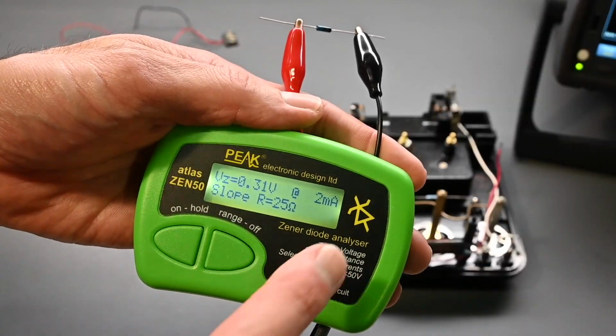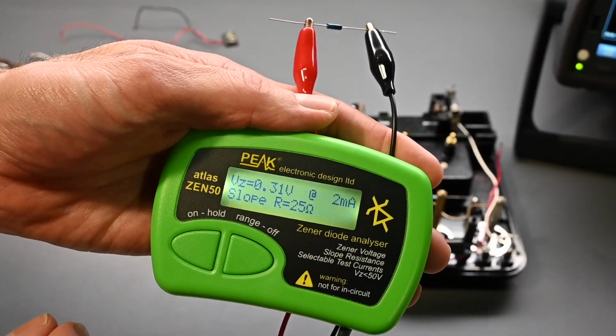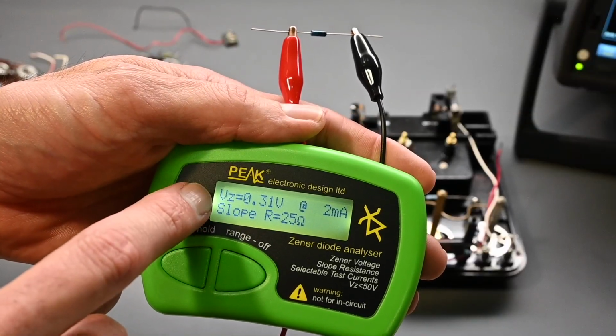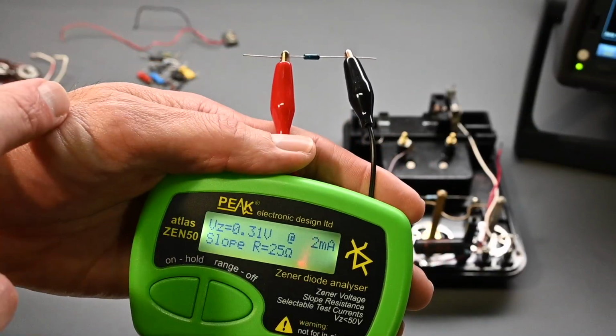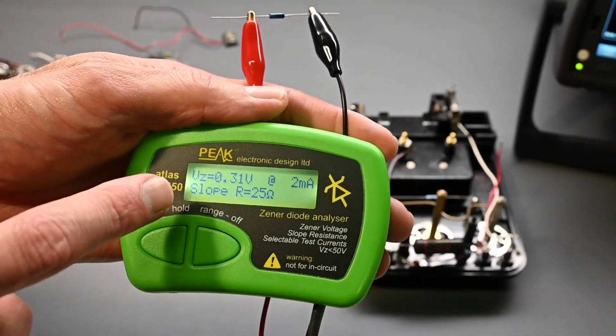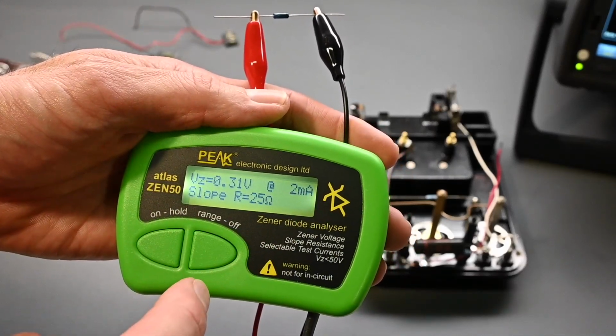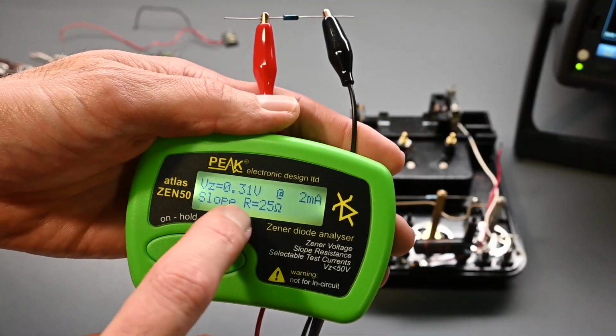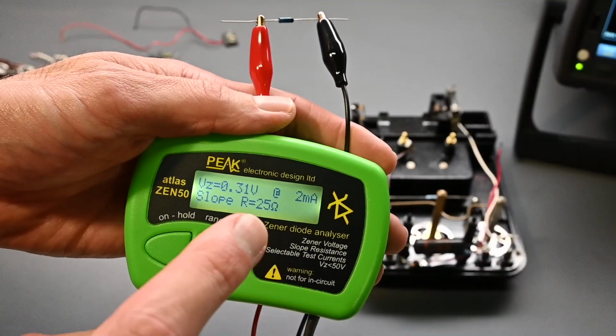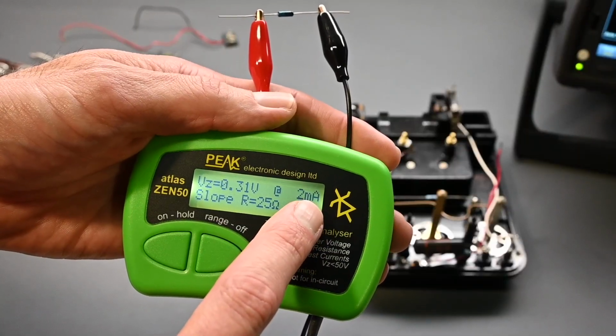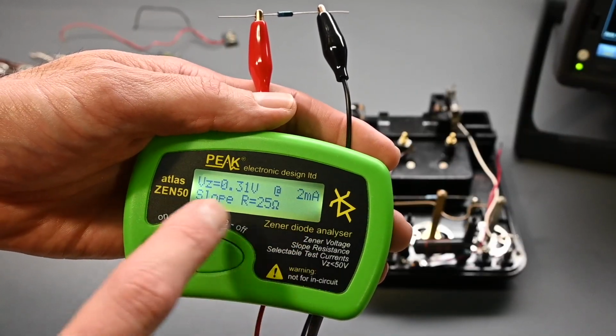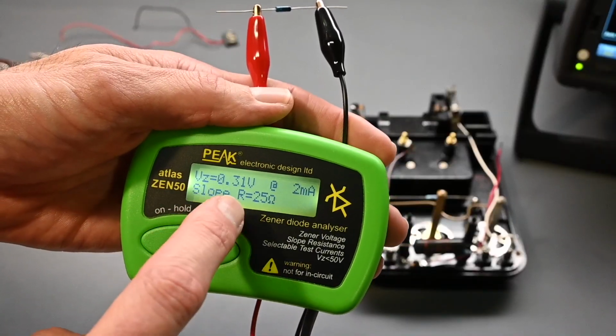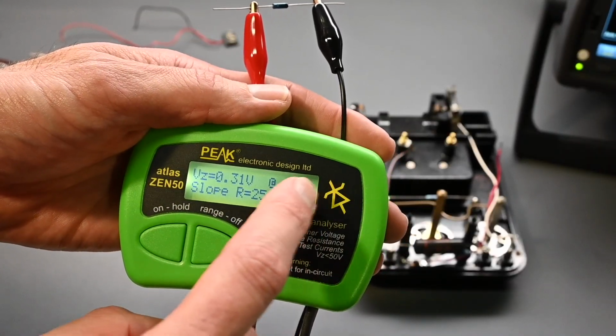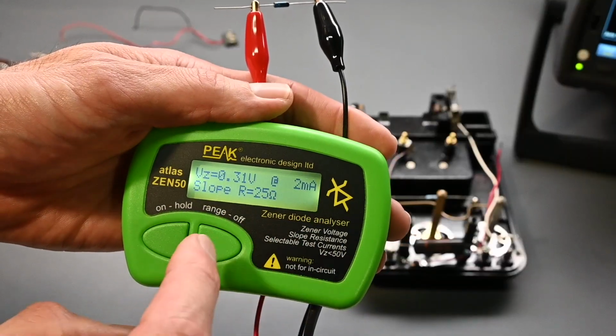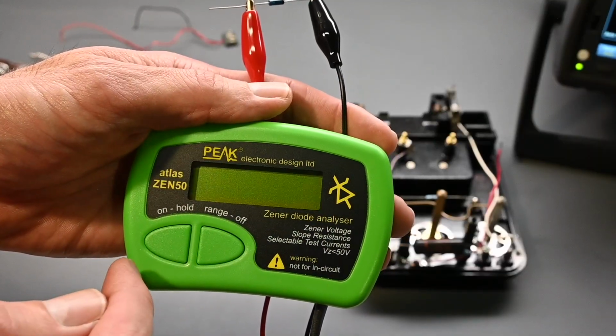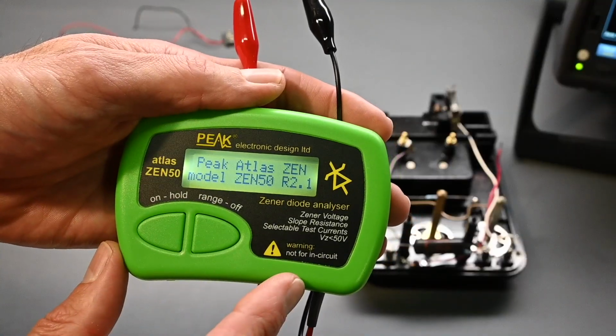So it starts with the 2 milliamps, so that's the current through the diode right now, and this, where it says VZ for voltage of the Zener, this is actually in a just regular diode like this, because this is not a Zener diode. This is just the forward voltage drop at this current. And then you can see right now the slope resistance. It says 25 ohms. So what this meter is actually doing is the current that you have right here, this is the middle current for the measurement on the slope resistance, and then it's measuring and figuring this value with a current that's a little bit higher than this value and also a little bit lower. So you have 3 points, and then it's coming up with this value based on those measurements. Oops, it turns off on its own.